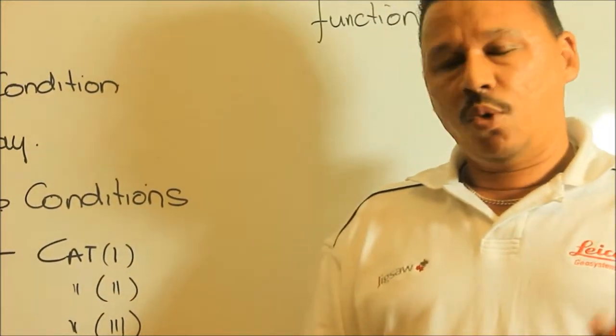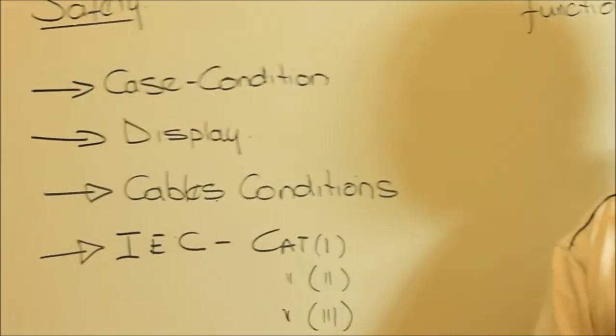Another important aspect is that multimeters have been put into certain categories by the IEC, the international regulation and standard. The categories range from 1 to 4, with category 1 being the lowest level and category 4 being the highest level. Category 1 multimeters and test leads can only be used on low voltage. Category 2 is good enough for single phase application.